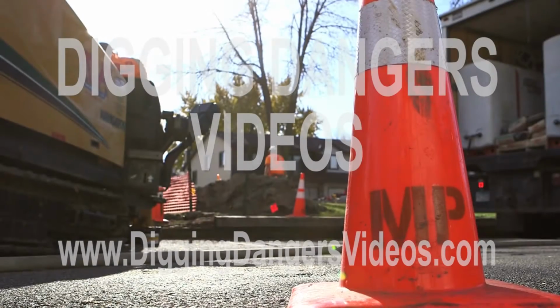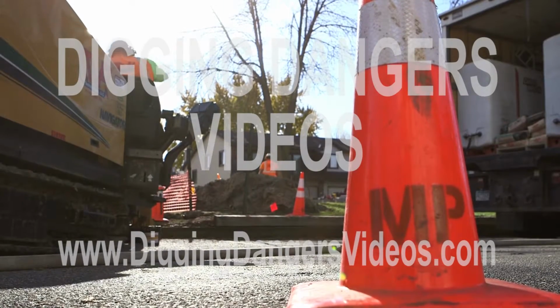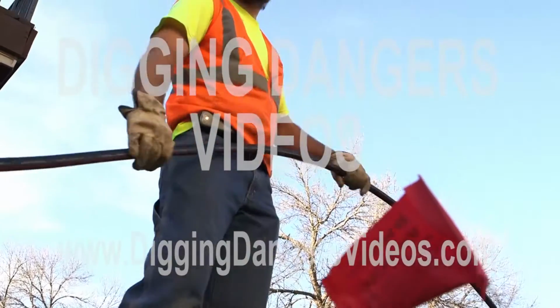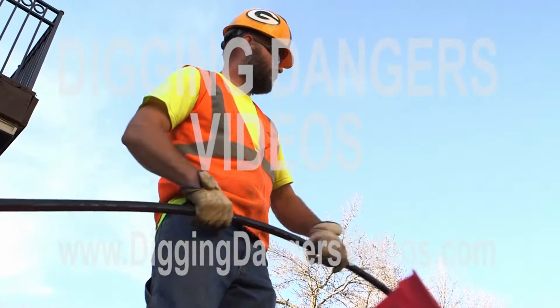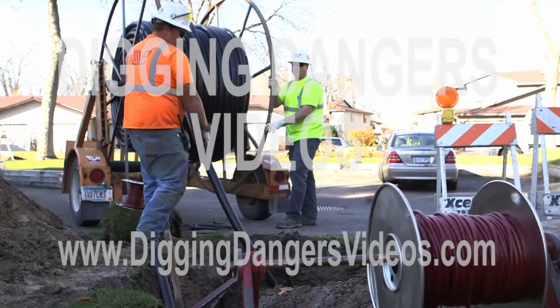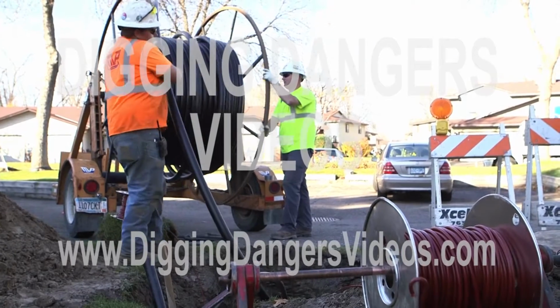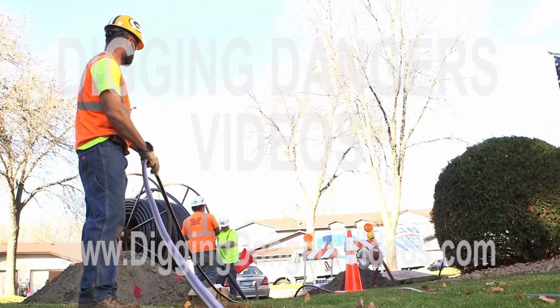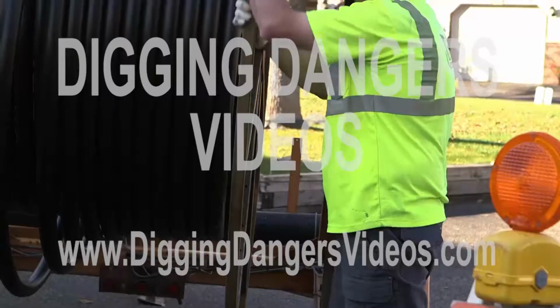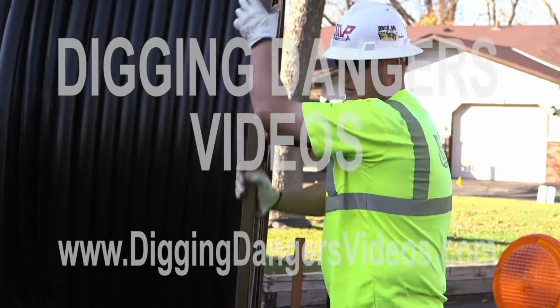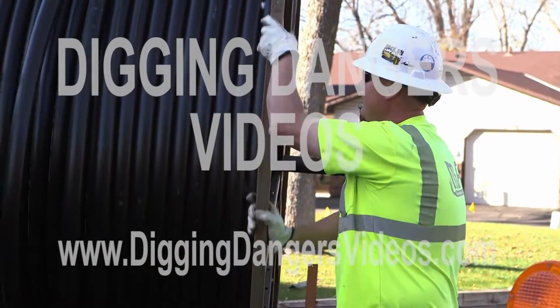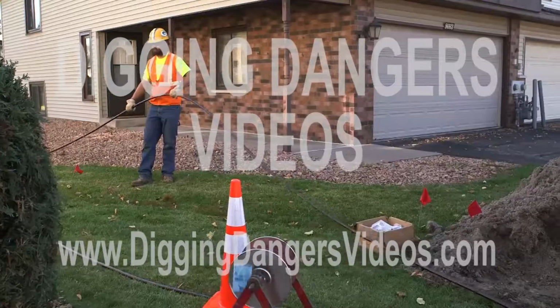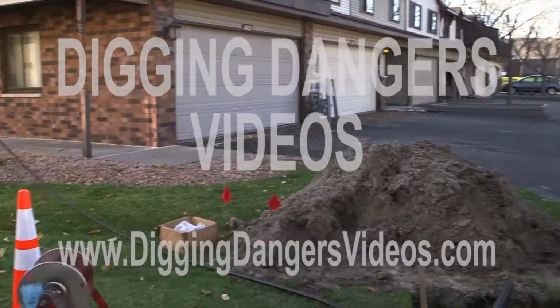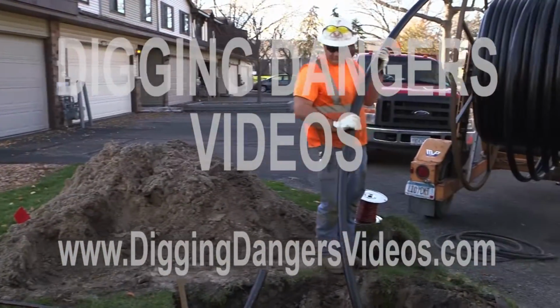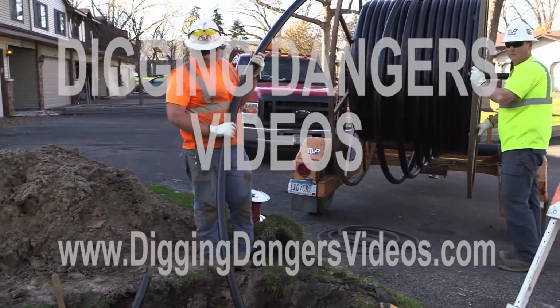For the safety of other people digging around power lines, make sure you use a steel conduit or galvanized conduit, gray PVC pipe, or black armor duct with the red stripe on it. You want to make sure that's identifiable as a power line in that ditch. If you use green sewer pipe or white sewer pipe, and that's something somebody might be expecting to be a sewer pipe when they cut into it, they could possibly cut into a cable.